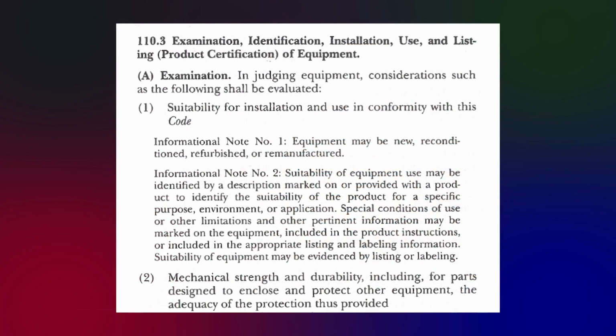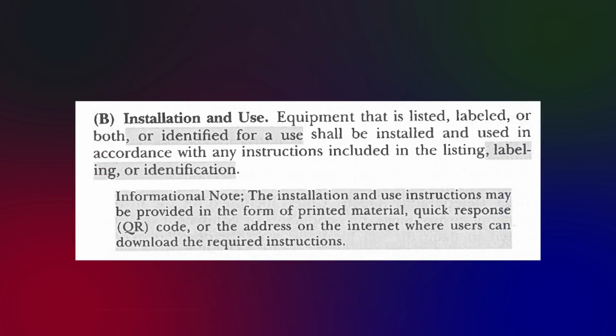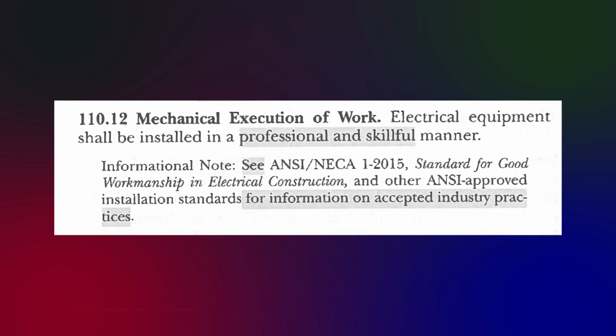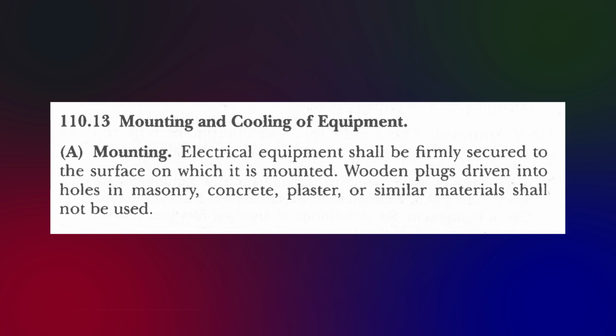The NEC states in Article 110.3, examination, identification, installation, use, and listing, product certification, of equipment, that mechanical strength, durability, and other factors must be considered. Article 110.3(B) says equipment must be installed in accordance with any instructions included with the equipment. The NEC also tells us in Article 110.12 that all electrical equipment must be installed in a neat and workmanlike manner. The NEC further guides us in Article 110.13(A) that all electrical equipment is required to be firmly secured to the surface on which it is mounted.